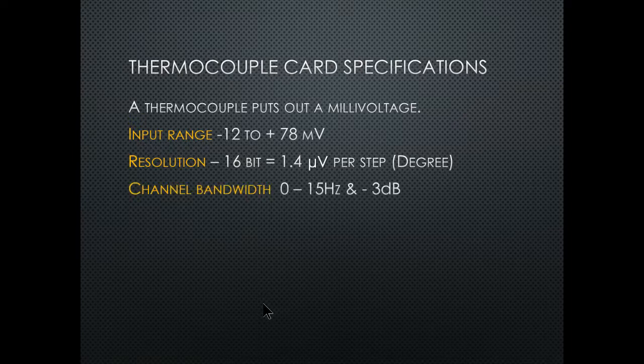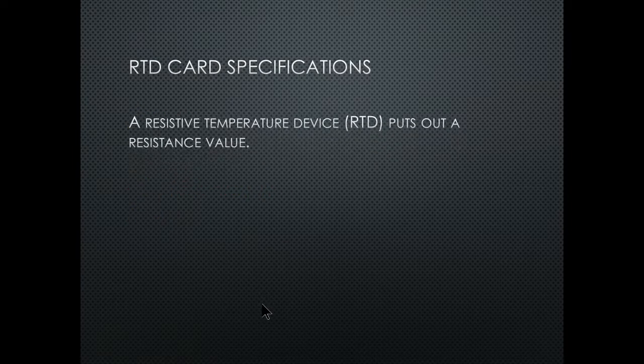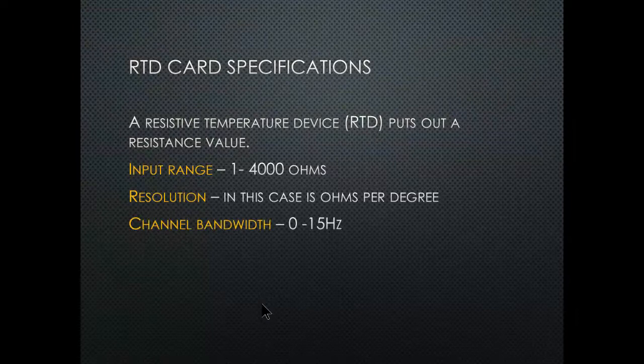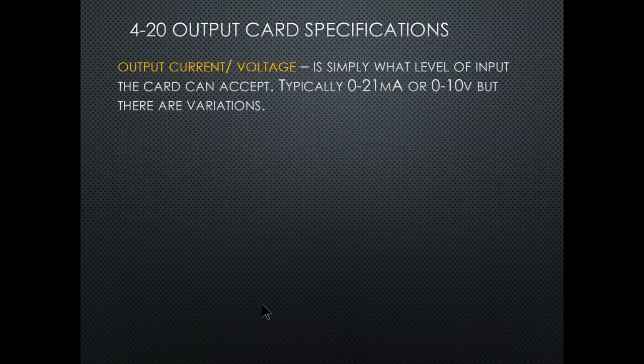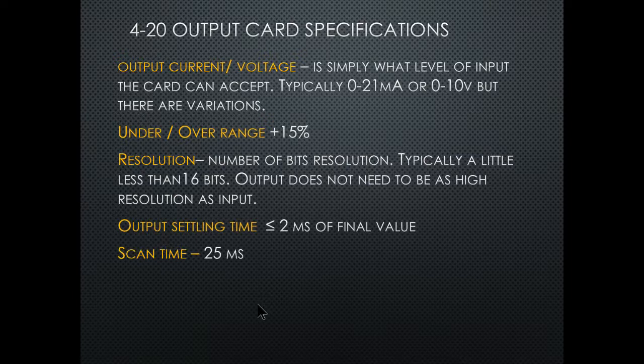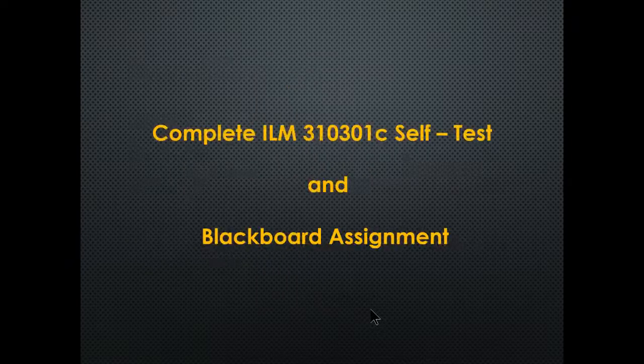An RTD card — resistive temperature device — puts out resistance values. The range is 1 to 4,000 ohms, resolution is approximately 1 per degree, channel bandwidth is 0 to 15 Hz, and scan time is 25 milliseconds. These specifications are all in the back of your book — don't worry too much about memorizing the exact values.